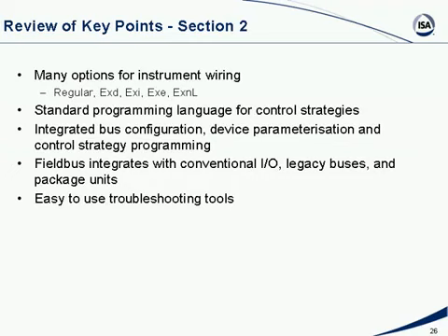Keep in mind that there are many solutions out there for running Fieldbus in hazardous areas. You can have a regular installation, an explosion-proof installation, or use intrinsic safety. You can use a combination of increased safety and intrinsic safety, or a combination of non-arcing and non-incendive approaches. So there are lots of different ways of running Fieldbus in hazardous areas.